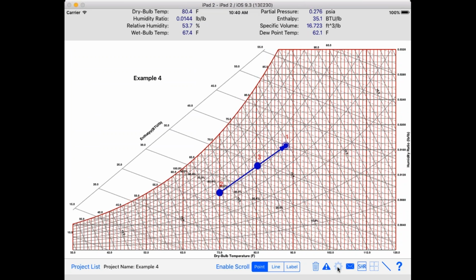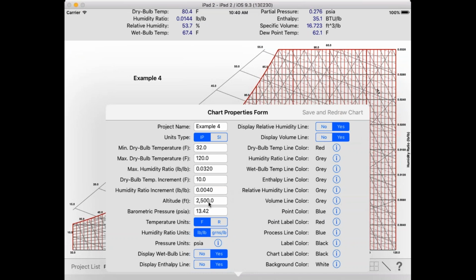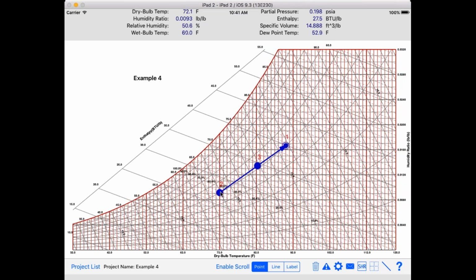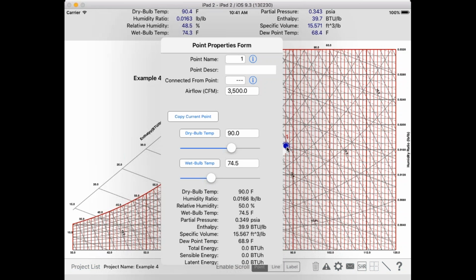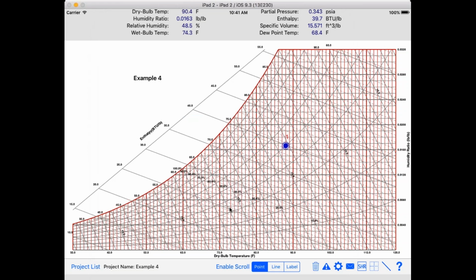Here's our chart. Let's look at the properties of this chart. We're at 2,500 feet elevation. Okay, I'm going to delete these points. We'll leave this outside air point. So we're at 90 degrees dry bulb, 74 degrees wet bulb. And let's plot our other point, which is at 72 and 50%.